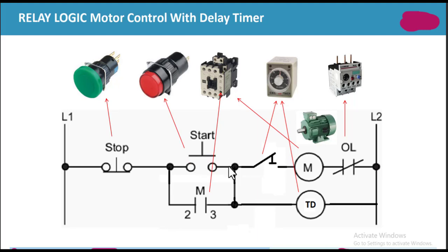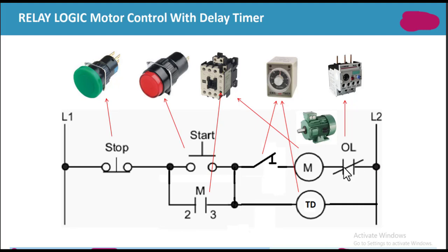This is the stop switch — when we want to stop the process we press this switch and the whole process will be terminated. When we click the start button, the motor will be in the running condition until the overload contactor becomes active. When the motor draws more current than its prescribed value, this overload relay will become active, it will be energized, and it will turn this switch open, terminating the whole process.